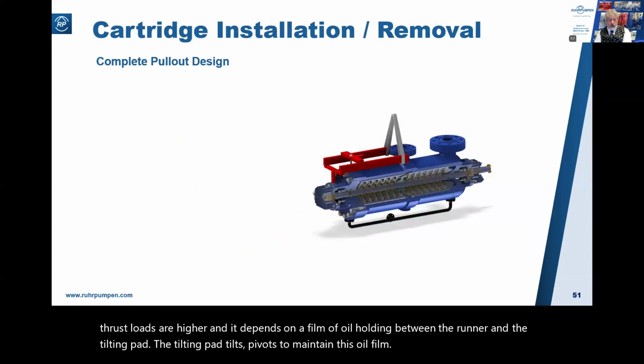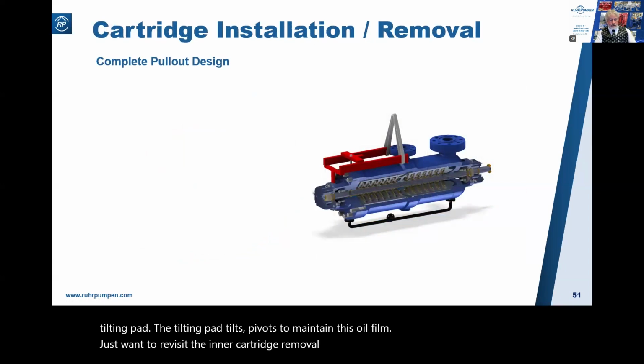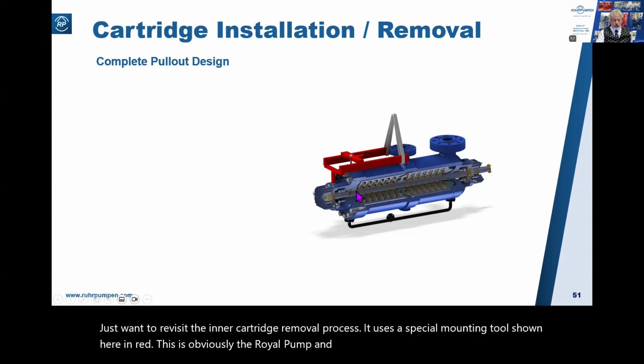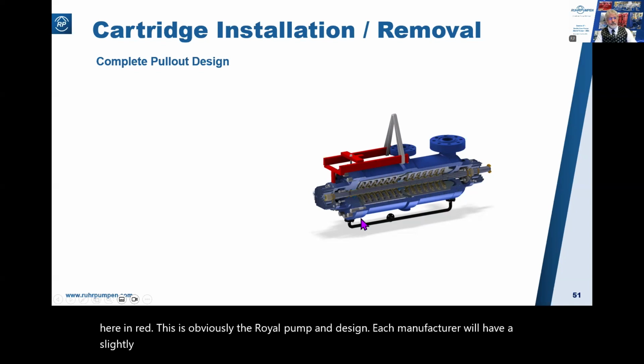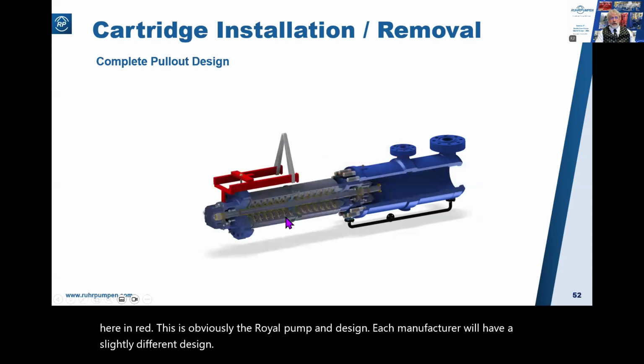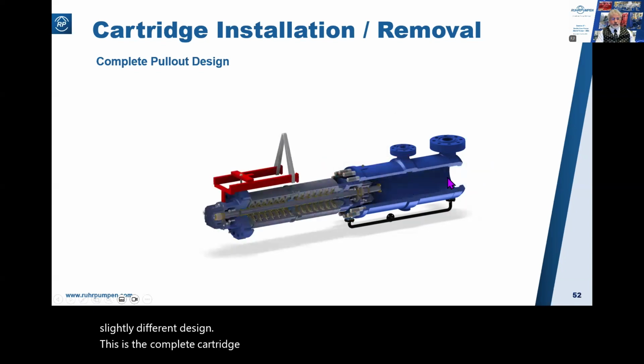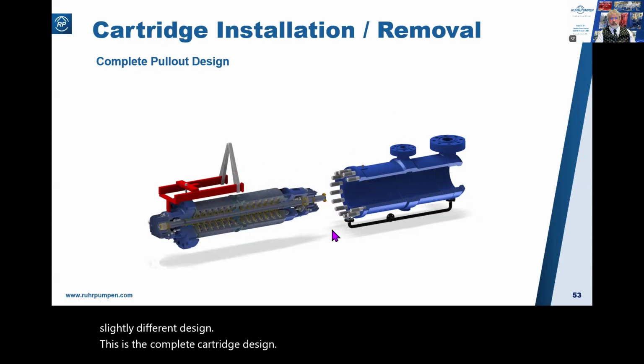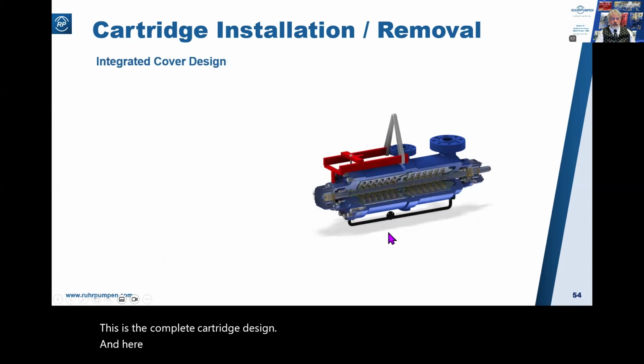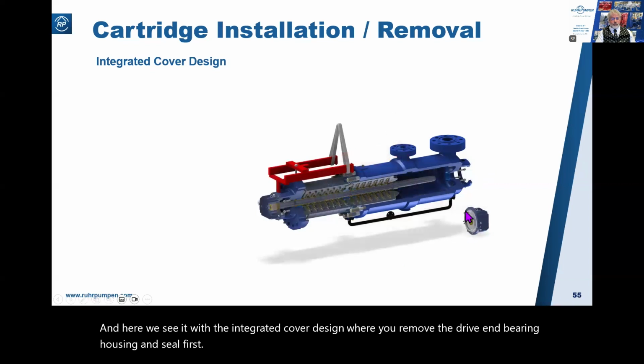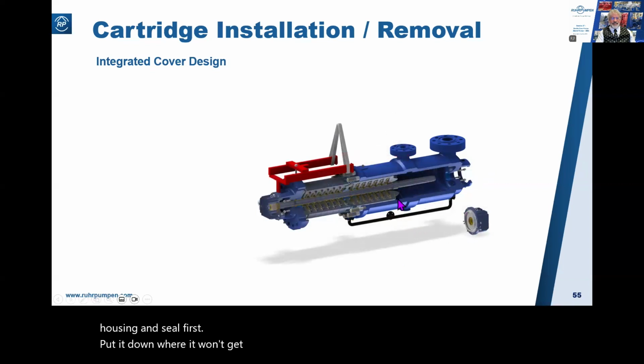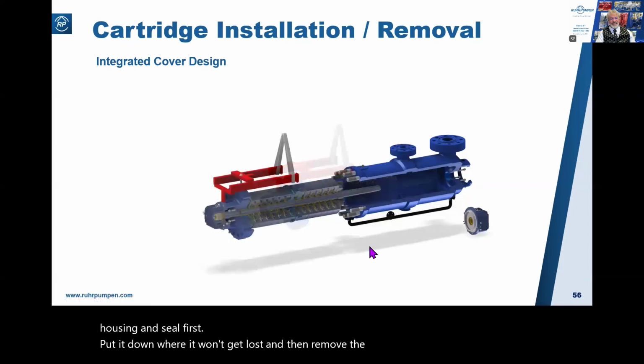Just want to revisit the inner cartridge removal process. It uses a special mounting tool shown here in red. This is obviously the Ruhrpumpen design. Each manufacturer will have a slightly different design. This is the complete cartridge design. And here we see it with the integrated cover design, where you remove the drive end bearing housing and seal first, and put it down where it won't get lost, and then remove the cartridge like this.